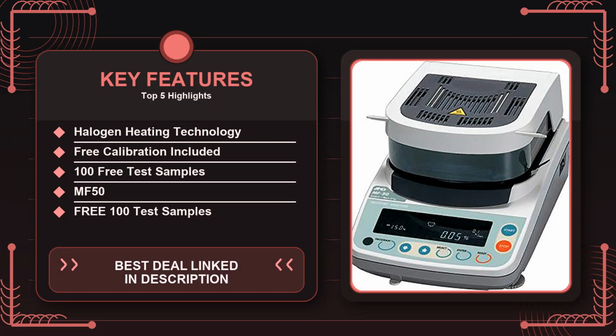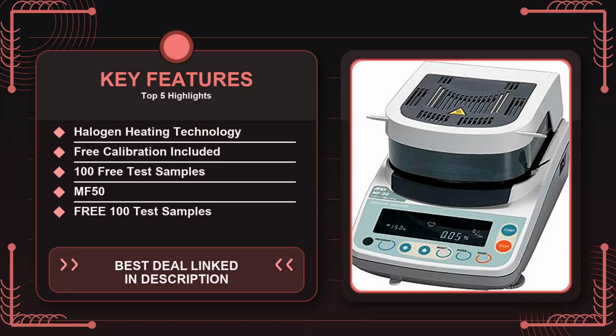If you run a small to medium-sized lab, a quality control station, or even a hobbyist setup where you need to validate material moisture content on a regular basis, the MF50 hits a sweet spot. The 51G capacity lets you handle a decent batch size without having to run dozens of microsamples, while the 0.002G resolution gives you the granularity you need for tight tolerance projects.